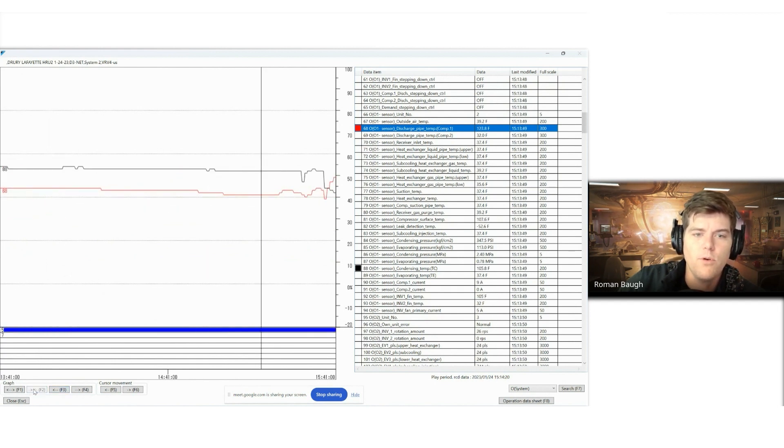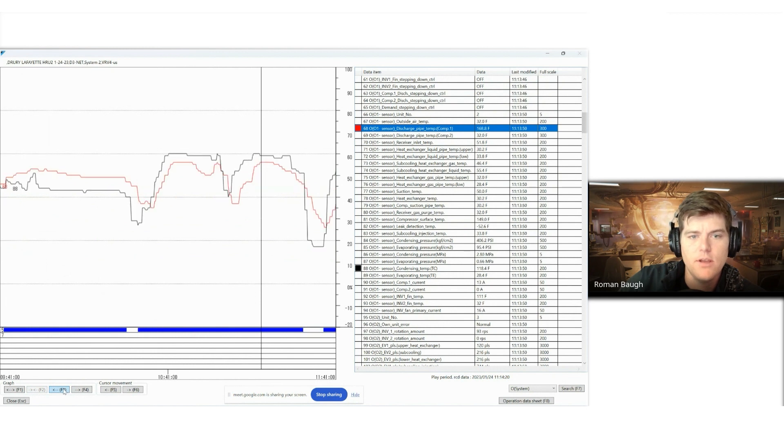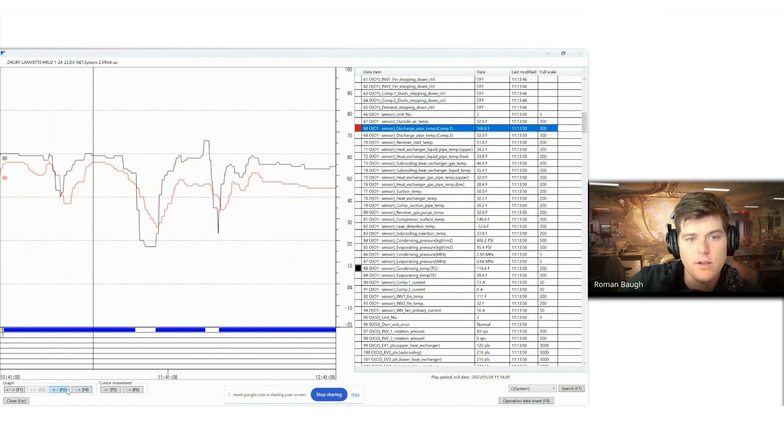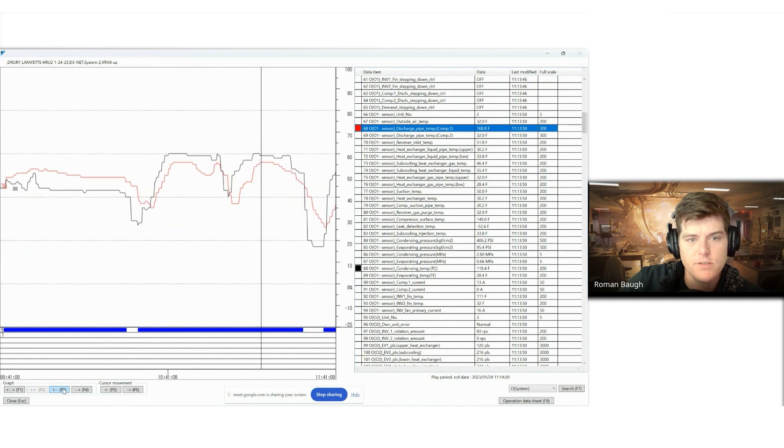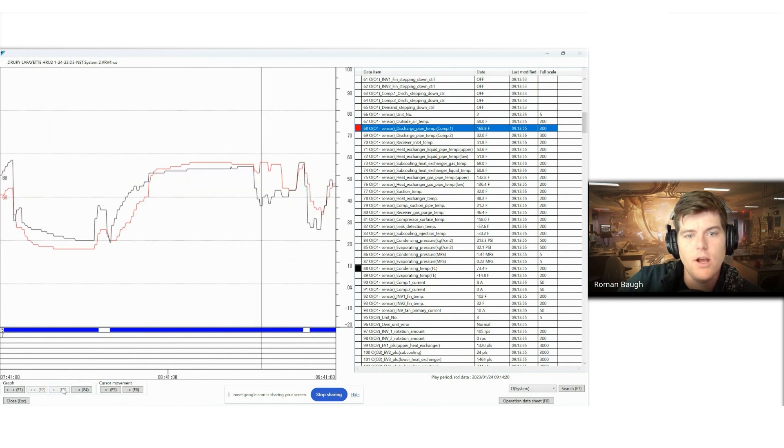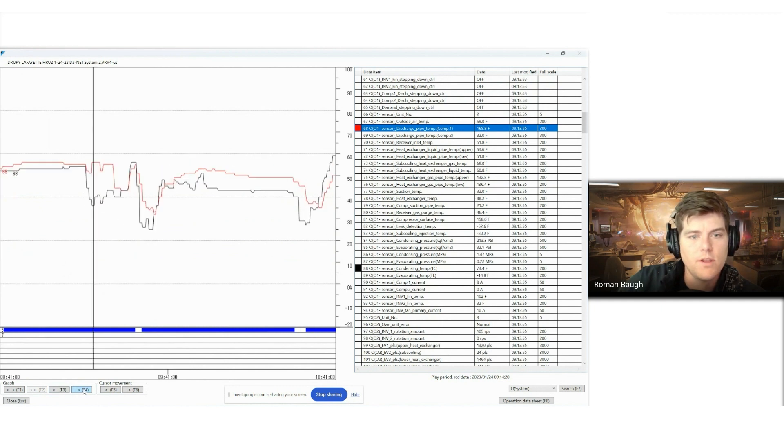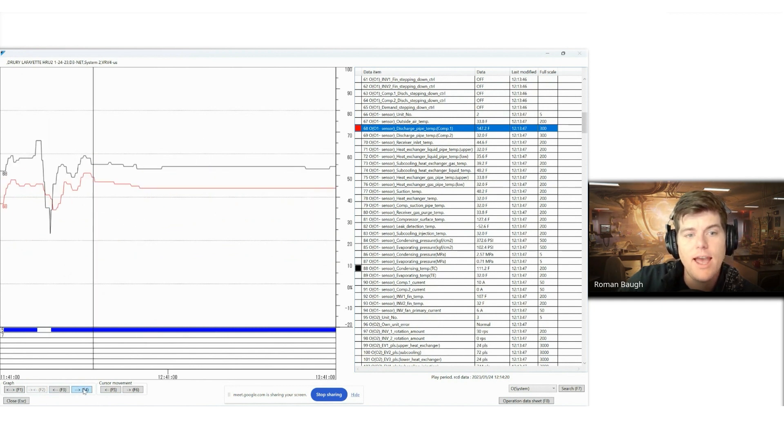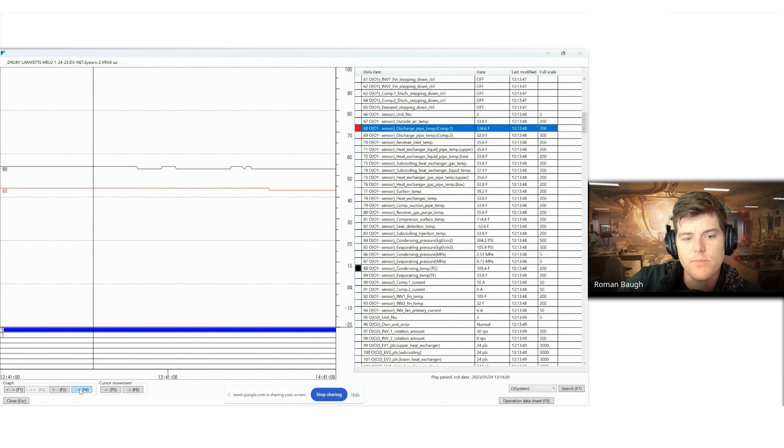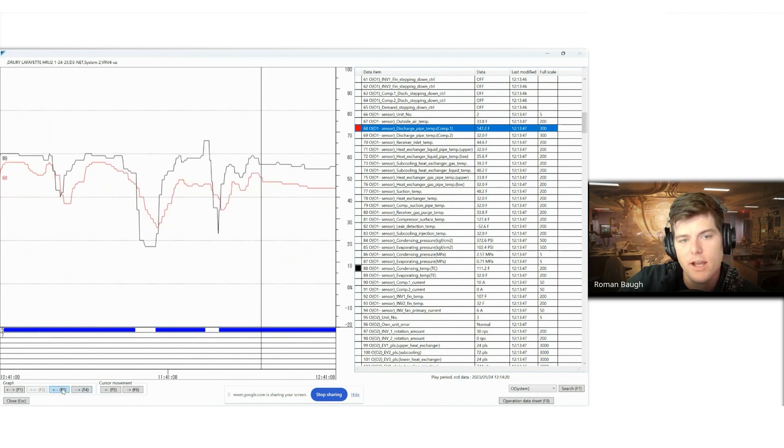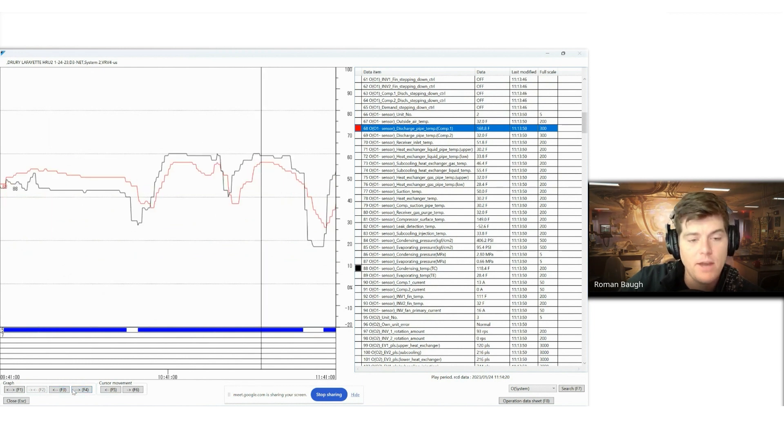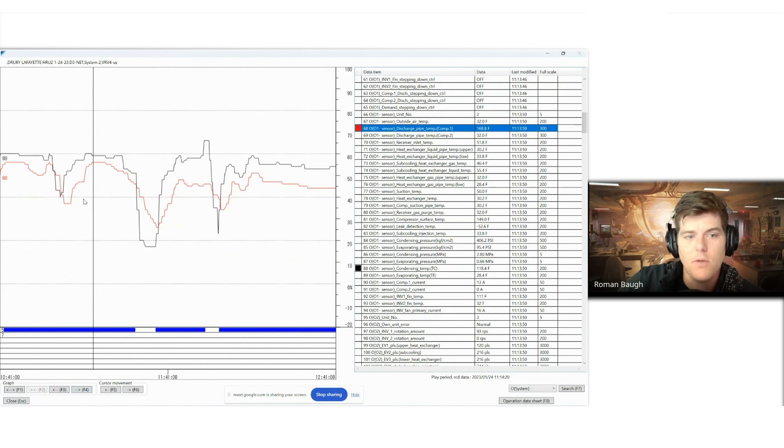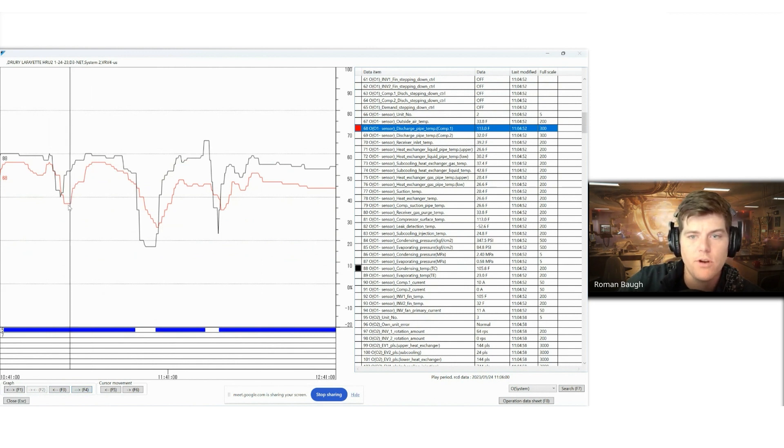Those are all the important things that we want to look at when we're talking about troubleshooting VRV systems, troubleshooting refrigeration systems in general. It's never one set of data. It's always how does the system progress and perform over a set period of time? Does it get better? Does it get worse? Does it stay the same? All of those things are important when we're talking about troubleshooting.